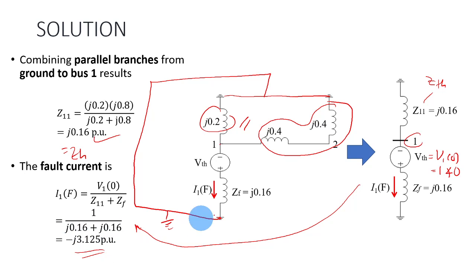The worst case, as you can see, is that if a fault occurred at bus number 1, you will have a higher value of fault current. So for the same network, for different locations of fault, we can have different fault currents. That's a very important lesson: although the pre-fault voltages are all the same, because of the different impedance that the faulted bus sees — the different location and impedance — you will see a different value of fault current.